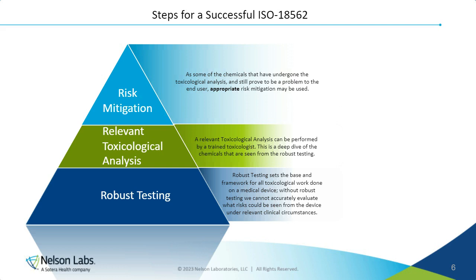As an outline for what makes a successful ISO 18562 toxicological risk assessment, we could use this pyramid, for example. On the bottom, we have robust testing, as the base of the pyramid will need to be the strongest part before you can continue to build. Here is where the medical device goes through all of the applicable testing. This is the most important part, as if the testing does not meet clinically relevant, there is really no point to run a toxicological risk assessment on the results.